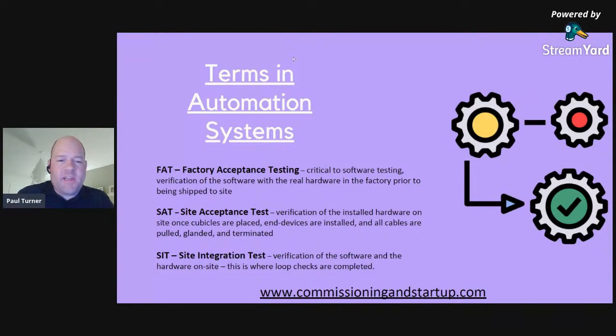The site acceptance test is confirmation that the hardware, once arrived at site, is installed correctly, all the cables are pulled, terminated correctly, and that end devices are installed correctly. So that site acceptance test would be one of the pre-tests to confirm prior to moving into commissioning. And then the site integration test is when the software is actually programmed into the hardware and the two can function on site.